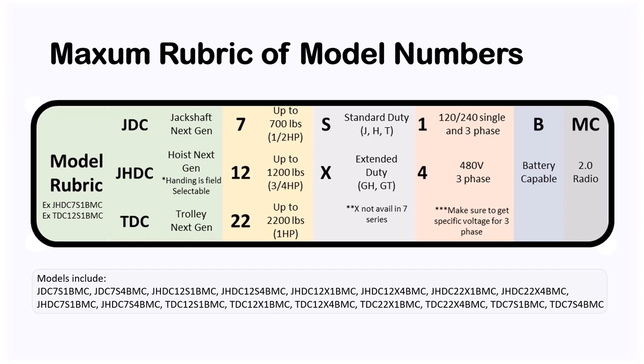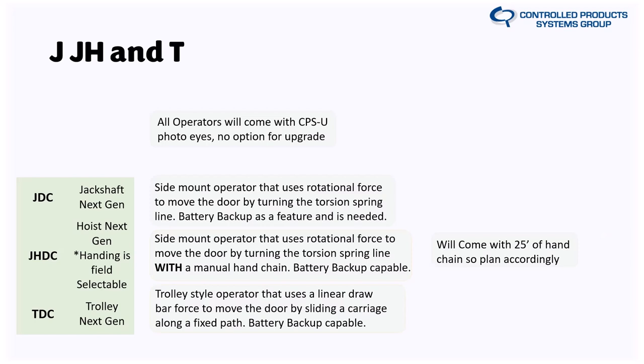The suffix 'BMC' means the unit is battery backup capable and has it on board. 'MC' designates the Security 2.0 radio set. There's also a NEMA 4 suffix that won't be released until early 2025, so I didn't include it here to avoid confusion at launch. Just to recap with examples: TDC12X4BMC is a trolley, 1200-pound series, extended duty, 480VAC, battery-capable. JHDC7S4BMC is a 700-pound series hoist jackshaft, 90 cycles per day, 480V. Note that the 7 series does not come in extended duty, and the 2200 series when released will not come in standard duty.